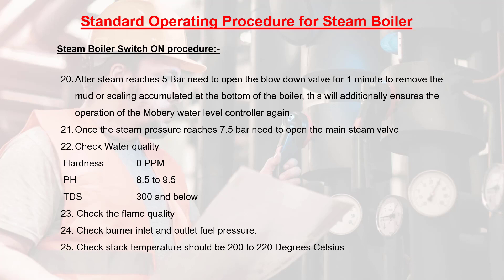Step 22: check water quality — hardness 0 ppm, pH 8.5 to 9.5, and TDS 300 and below. Step 23: check the flame quality. Step 24: check burner inlet and outlet fuel pressure. Step 25: check stack temperature, which should be 200 to 220 degrees Celsius.